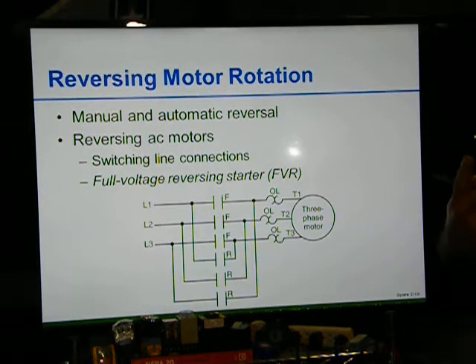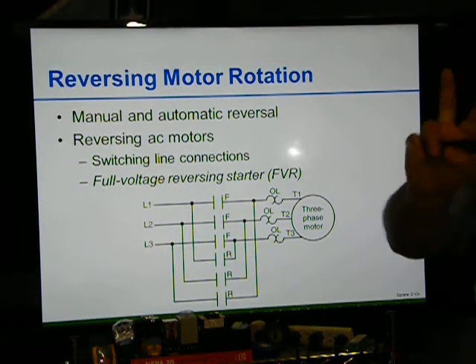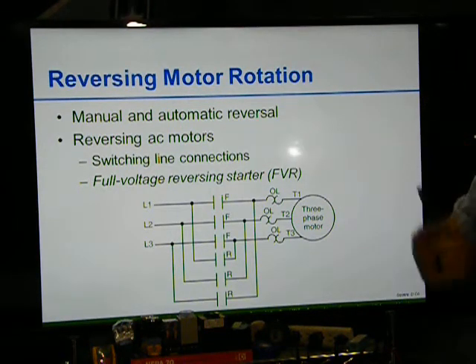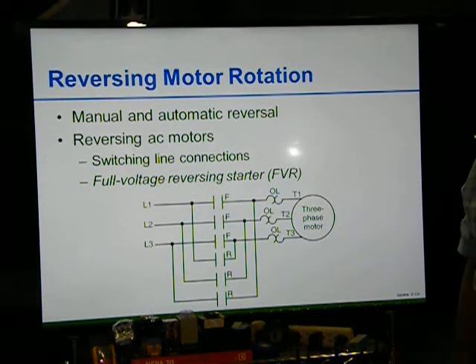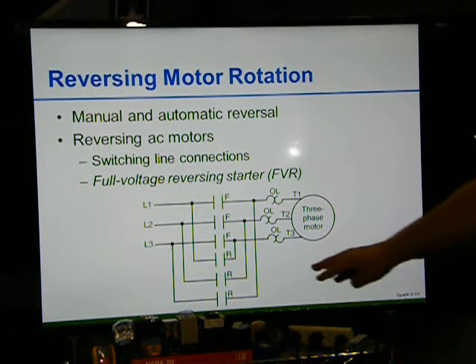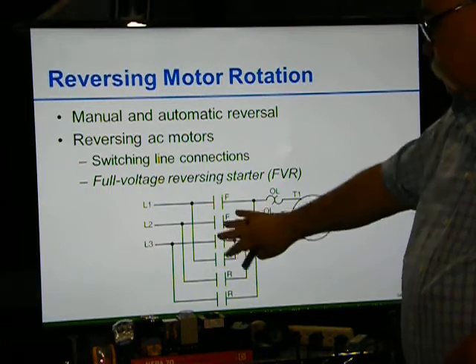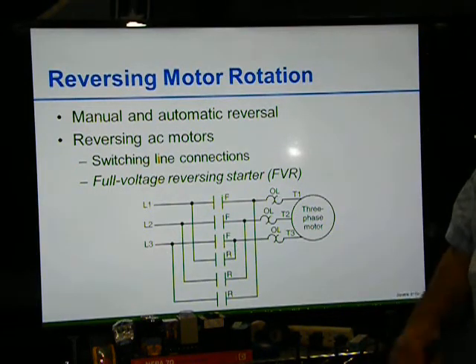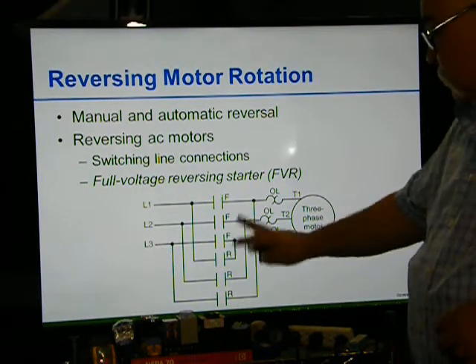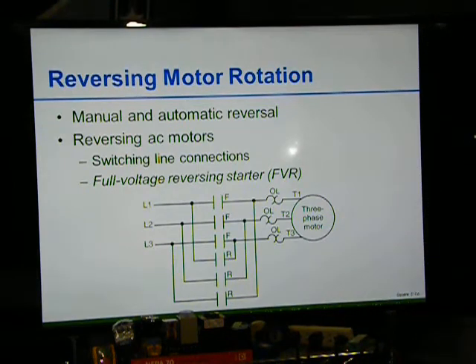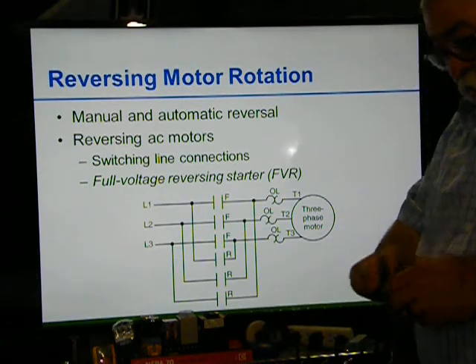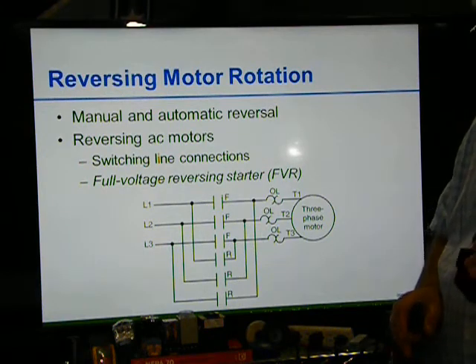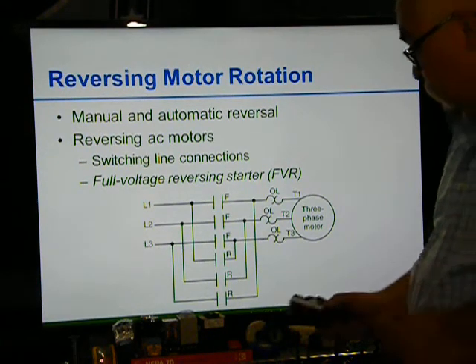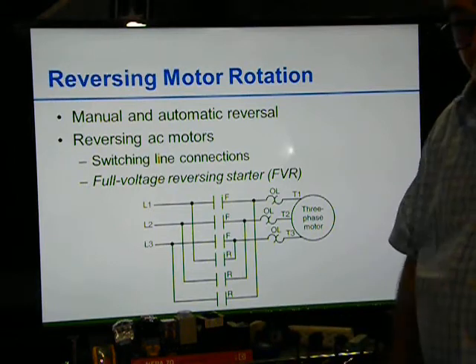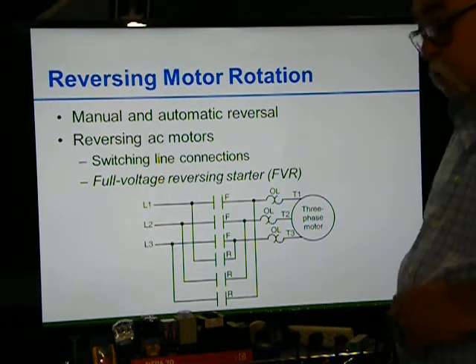I got these coming this way, and then instead of putting them this way, I do it this way. So now the motor goes in reverse. Not a good way to do it. It's always better to have a full voltage reversing starter, and it has interlocks that don't allow one to start from the other. Sometimes you can use overloads to protect it, but you only need the overloads on one. So you're gonna take care of reversing the motor.